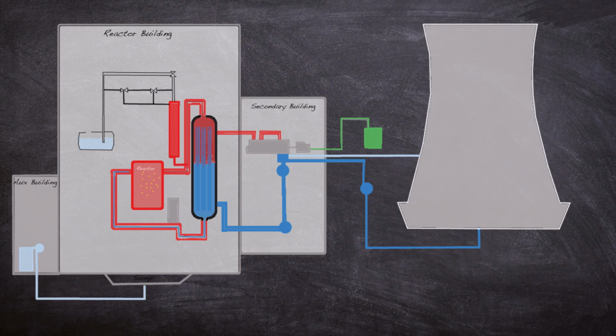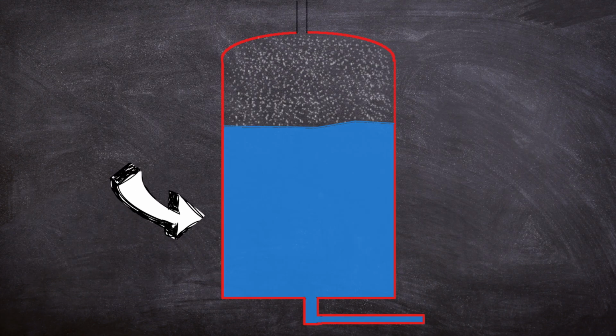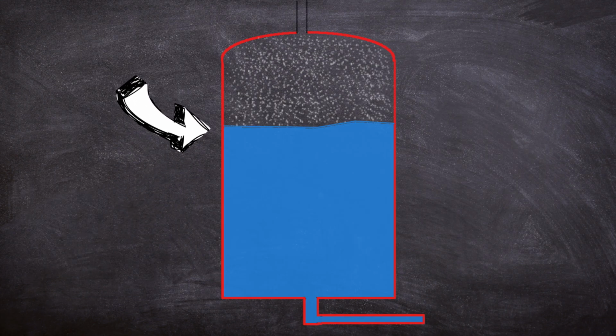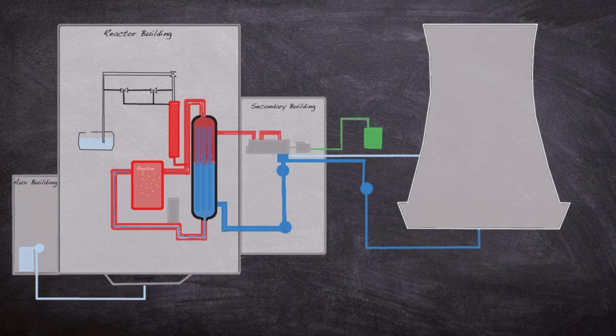Connected to the primary circuit are pressurizers filled about halfway full of water with a steam cushion on top. The pressure in the system can be controlled by either heating up with electric heaters or cooling down with a water spray on the pressurizers. This ability to change the pressure can be used either by the control system or the plant operators.